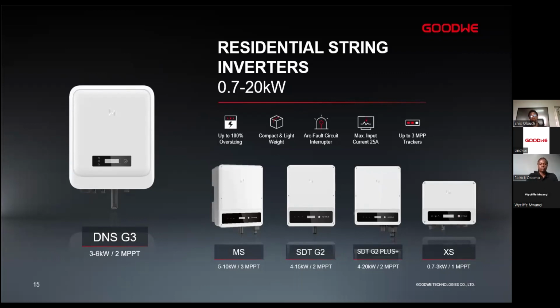They are compact and lightweight. Just as an example, the XS series is the size of an A4. Then in terms of safety, it can be integrated with the AFCI, and SPD on the AC and DC are available for all inverters. They have a maximum current input of 25 amps. Therefore, they are compatible with most high power modules, and they have up to 3 MPPT trackers. Therefore, you can do stringing on various orientations.